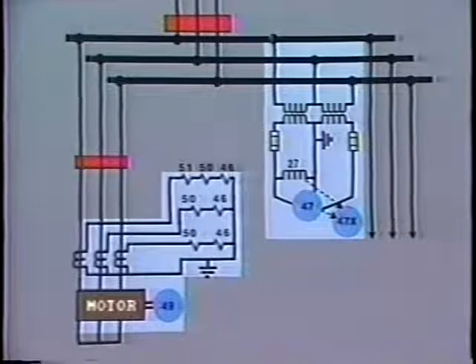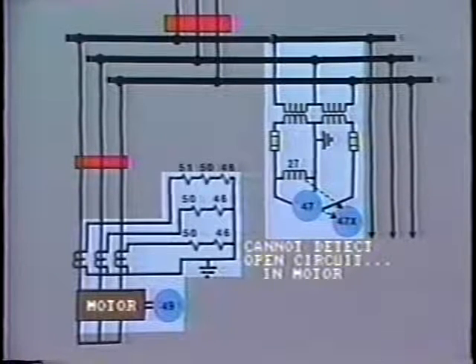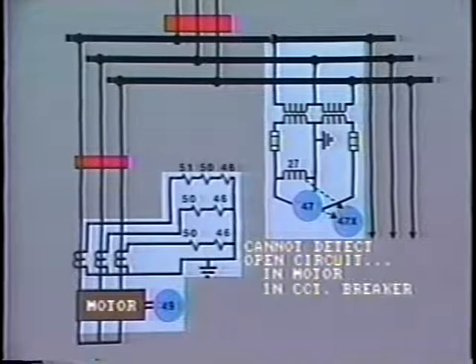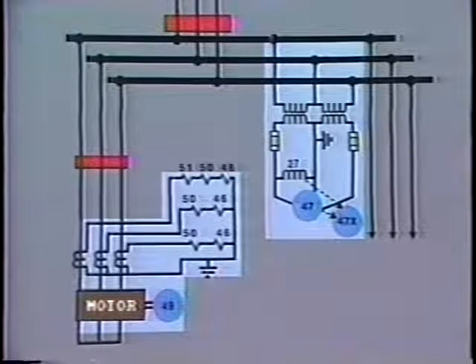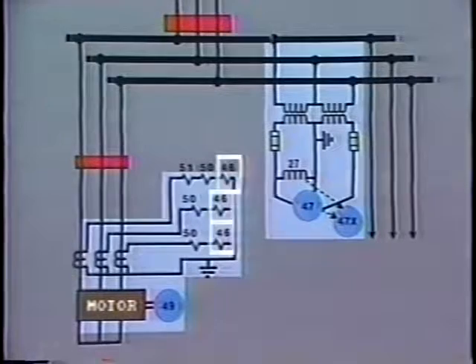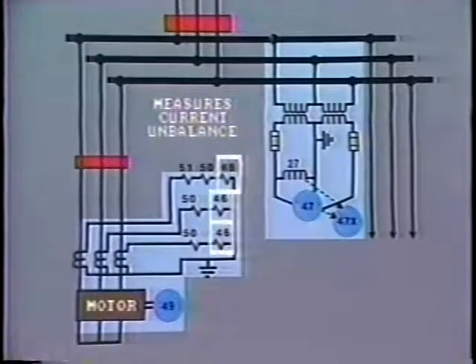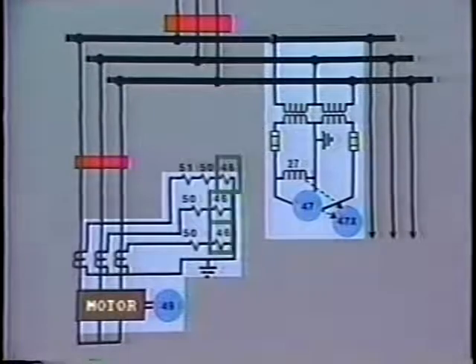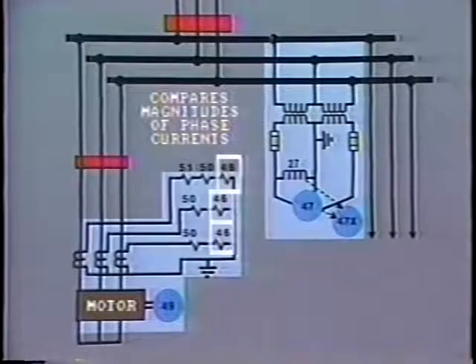As before, we have a negative sequence relay connected to the supply bus. In the case of unbalanced system conditions, this would trip all of the motors on that bus. One problem with this arrangement is that it cannot detect an open circuit inside the motor itself, or the circuit breaker, or the supply leads. For this reason, on large motors, an additional relay is often fitted to measure current unbalance. This is fed from the same CTs as the overcurrent relay. The phase balance relay, 46, consists of an induction disc which compares the magnitudes of the phase currents. When the motor is running at close to full load, the phase balance relay will operate if the unbalance reaches 15% or more.